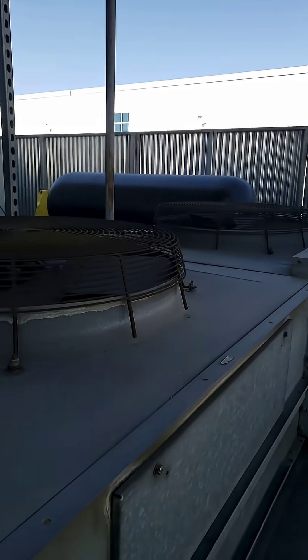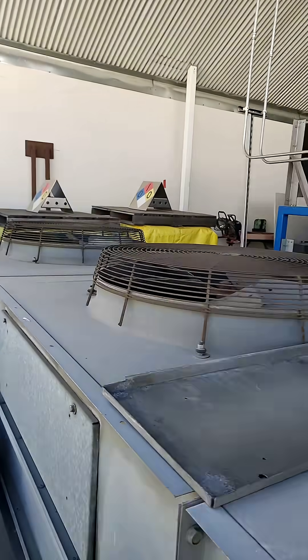Today we got a call about a condenser motor that is not functional. We have a large five-motor condenser unit and this motor is not functional. I've already opened up the hatch and felt whether it was the bearings that were seized up or if it was an electrical issue.